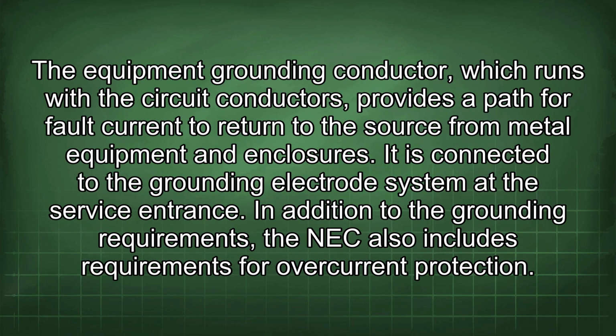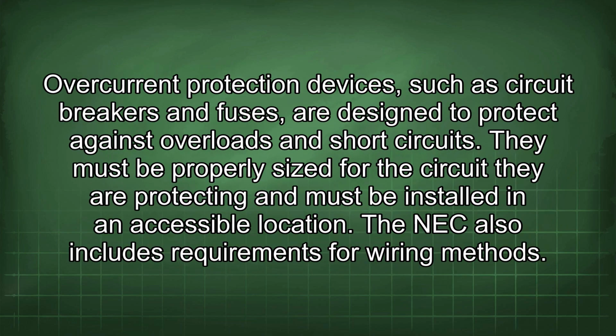This helps to stabilize the voltage of the electrical system and provides a reference point for grounding. The equipment grounding conductor, which runs with the circuit conductors, provides a path for fault current to return to the source from metal equipment and enclosures. It is connected to the grounding electrode system at the service entrance. In addition to the grounding requirements, the NEC also includes requirements for overcurrent protection. Overcurrent protection devices, such as circuit breakers and fuses, are designed to protect against overloads and short circuits. They must be properly sized for the circuit they are protecting and must be installed in an accessible location.